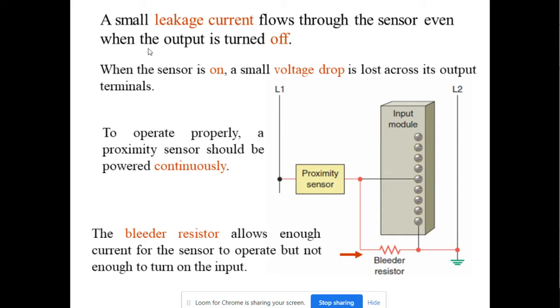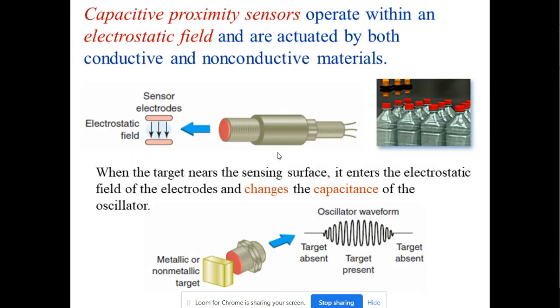A small leakage current flows through the sensor even when the output is turned off. When the sensor is on, a small voltage drop is lost across its output terminal. To operate properly, a proximity sensor can be powered continuously. The bleeder resistor allows enough current for the sensor to operate but not enough to turn on the input. This is one of the ways how we can use this proximity sensor.